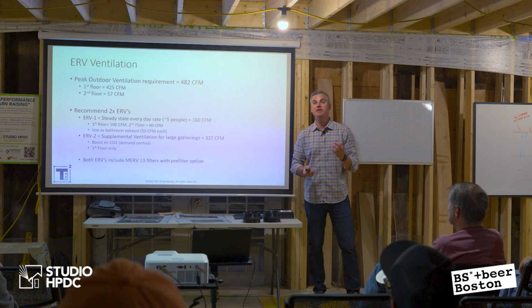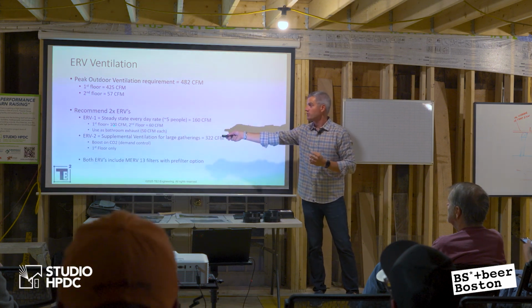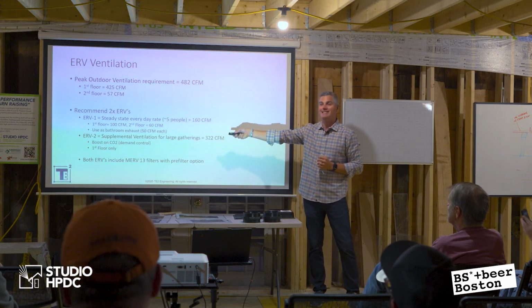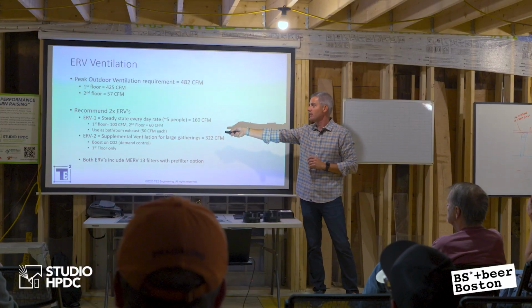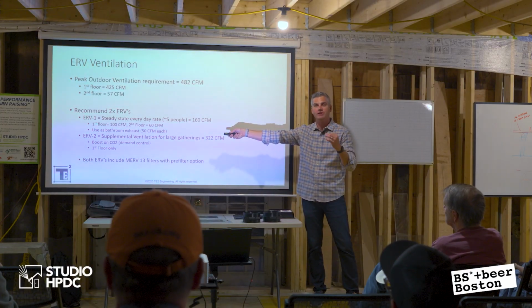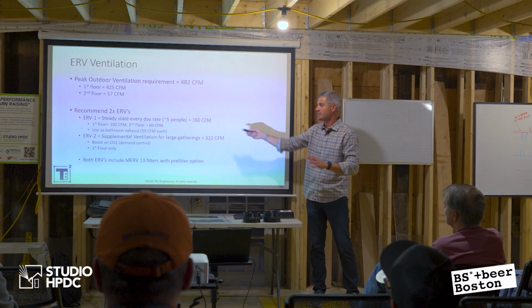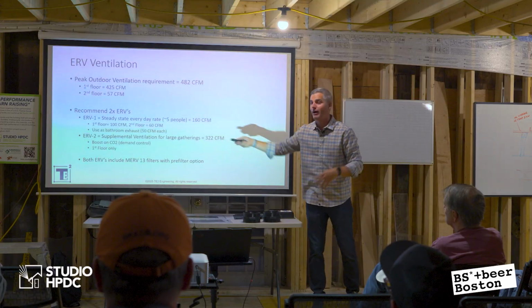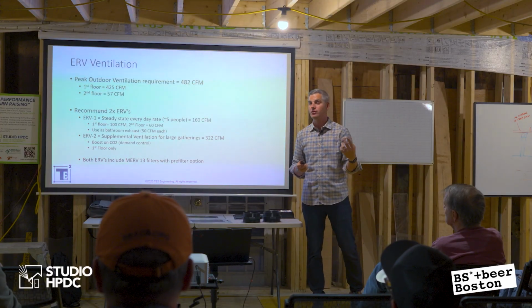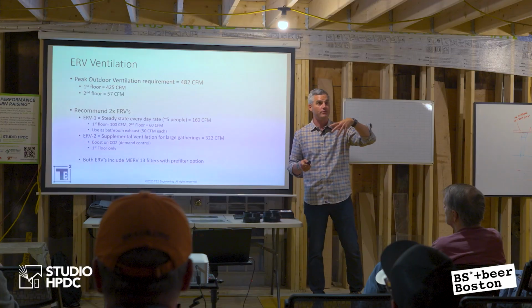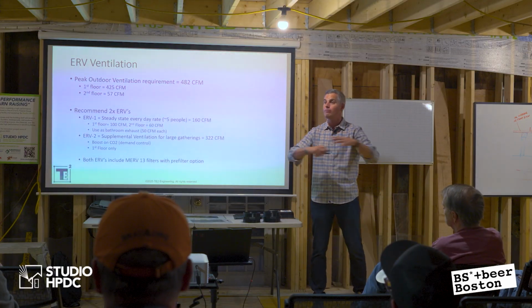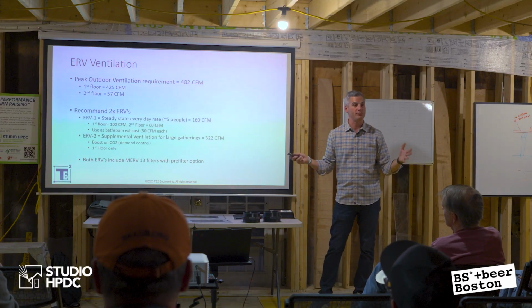That's gonna be 160 CFM. So the first floor is going to get 100 CFM of ventilation air, second floor is going to get 60. So I solved the second floor ventilation with that unit, and I solved the everyday use case for the first floor space. 160. I also use that unit to do my bathroom exhaust. So I killed 2 birds with 1 stone. I get my ventilation and I get my exhaust for my bathrooms, right? And that will handle most of the conditions for the ventilation for this building.